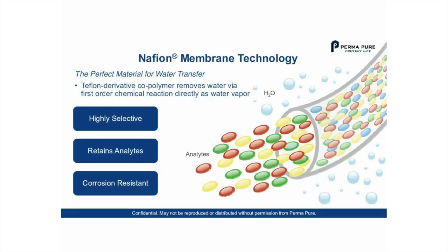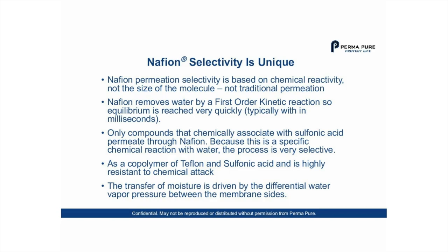All of these humidifiers are based on Nafion membrane technology. Nafion is the perfect material for water transfer — it is a Teflon derivative copolymer that removes or adds water via a first-order chemical reaction directly as water vapor. Nafion's permeation selectivity is based on chemical reactivity, not the size of the molecule, so it is not traditional permeation.